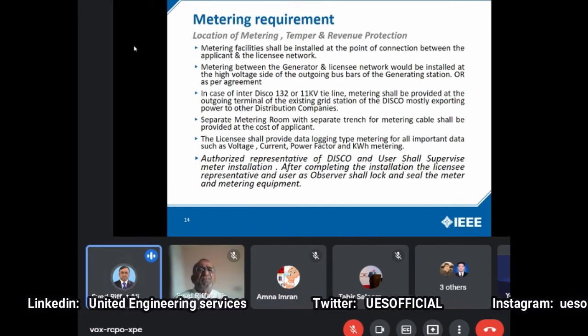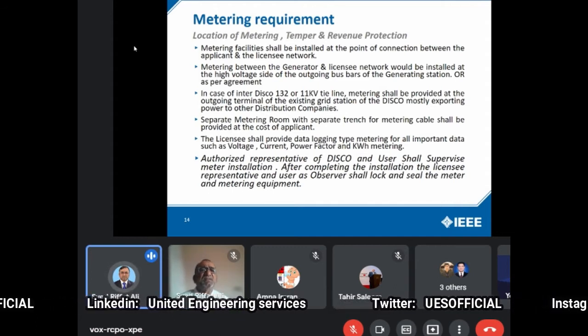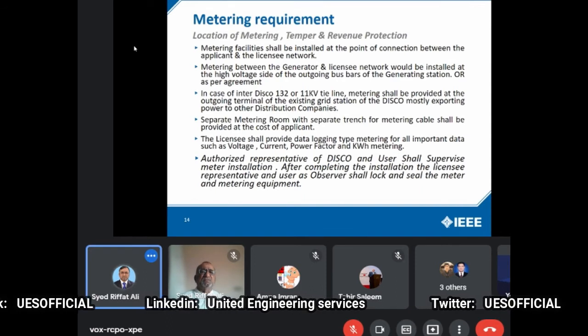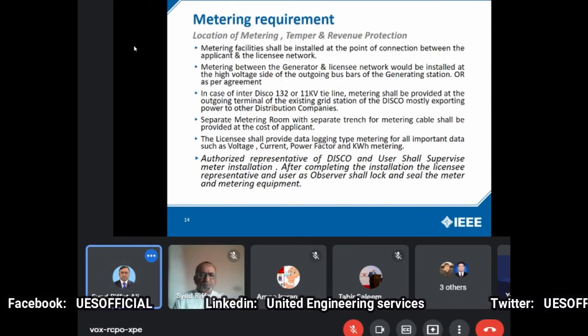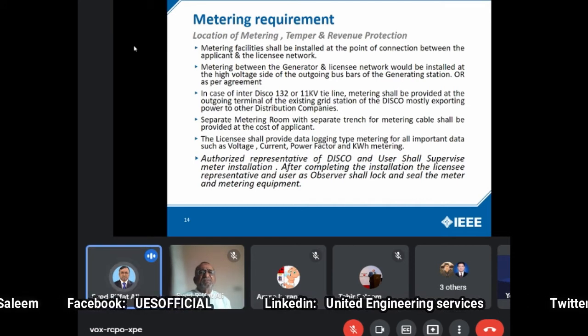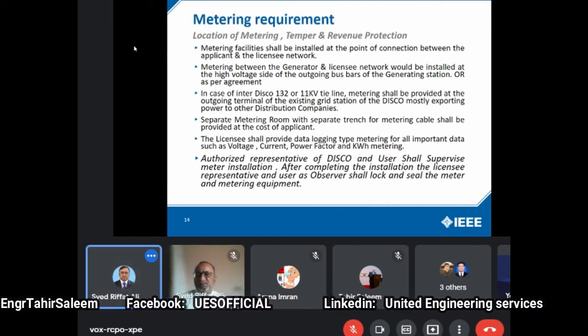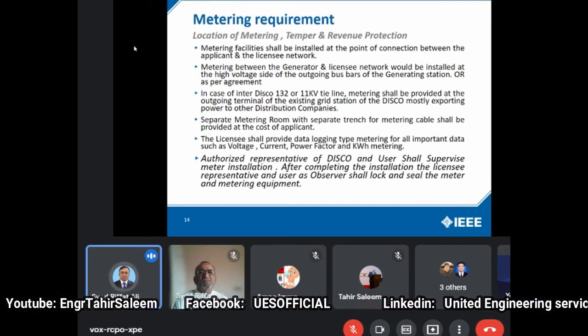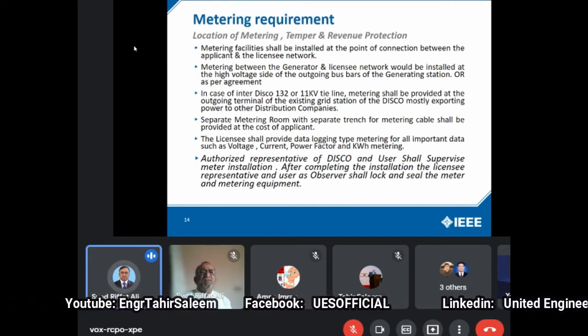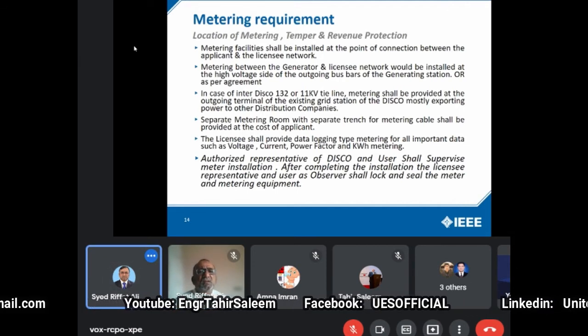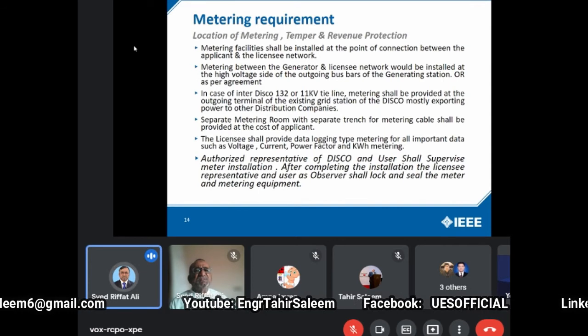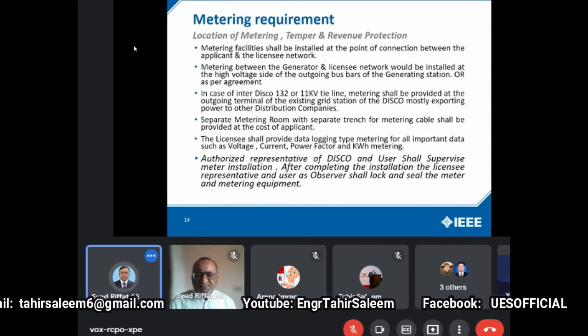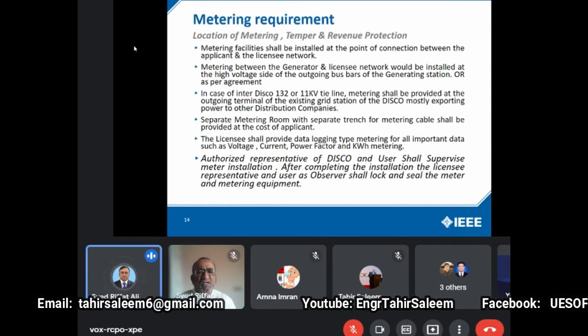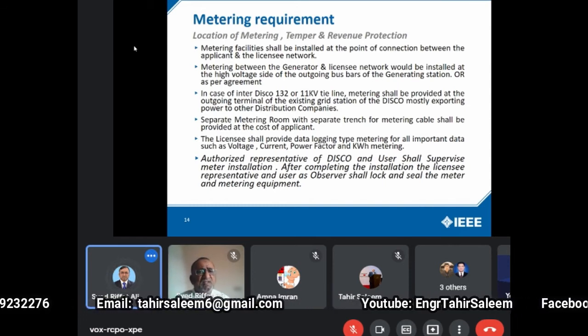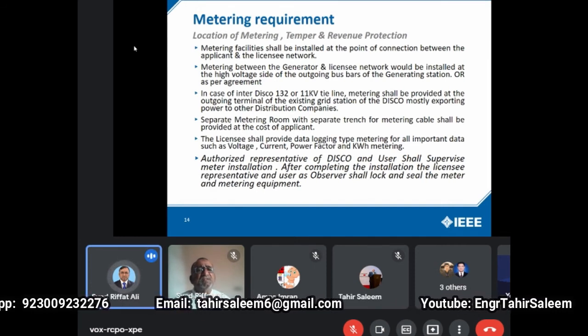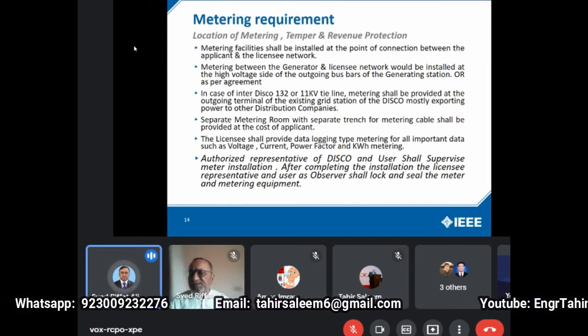So let us read. Metering facility shall be installed at the point of connection between the applicant and the licensee network. Bulk supply consumers, the distribution companies of the WAPDA or now the independent distribution companies, they supply bulk supply to the individual consumers, and a separate metering room is required as per the specification. And now this is also incorporated in this subcode, that a separate metering room is provided.